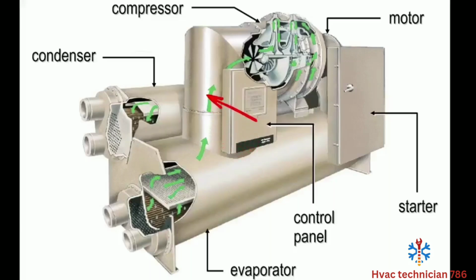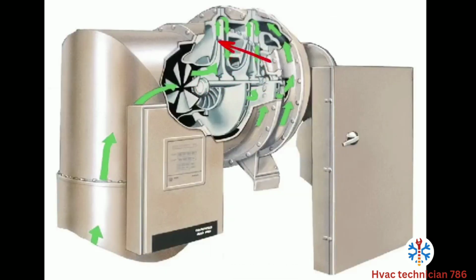Diving right in on this CVH chiller, we're going to come up our suction line and into our suction elbow off of the evaporator. This is going to go straight into our suction nose cone where we hit our IGV. This is actually our first stage of IGV. IGV stands for inlet guide vane, where we then pass to our first stage impeller. And we're going to pass through this first stage up into our diffuser. This diffuser is going to feed directly into the second stage.